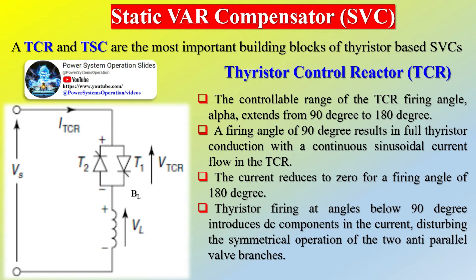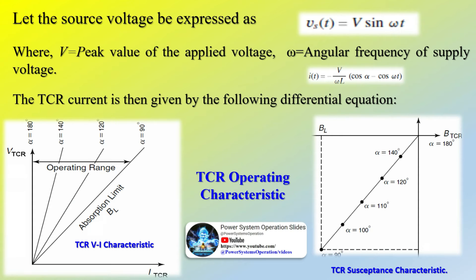Static VAR Compensators (SVC) are shunt-connected static VAR generators and/or absorbers whose outputs are varied to control specific power system quantities. The term 'static' denotes that there are no moving or rotating components. Basic types of SVCs include: thyristor-controlled reactor (TCR), thyristor-switched capacitor (TSC), and saturated reactor. A static VAR system (SVS) is an aggregation of SVCs and mechanically switched capacitors or reactors whose outputs are coordinated. When operating at its capacitive limit, an SVC behaves like a simple capacitor.